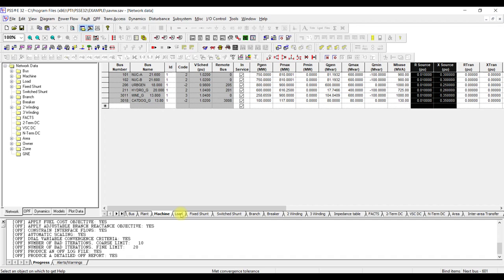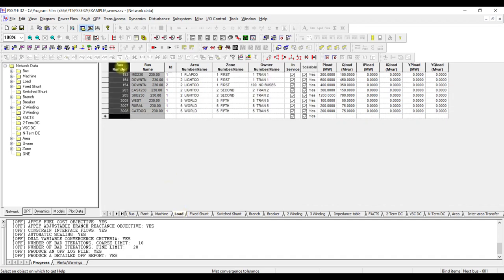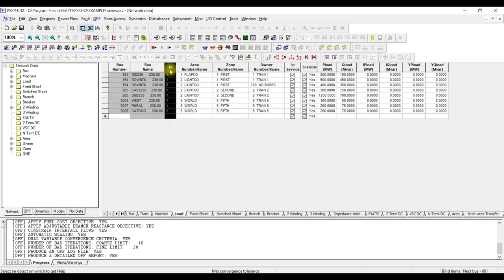Now let's talk about the Load tab. In the load, you have the bus name, bus number, and the ID because on one bus you can have multiple loads. The load can belong to different areas, different zones, and different owners. The in-service and out-of-service option lets you choose whether this load should be considered in the analysis or not. Scalable means that once you have this load, you can scale it up or down — since load in a power system does not remain the same, you can adjust the load values accordingly. Then you have active and reactive power fields where you give the load values.